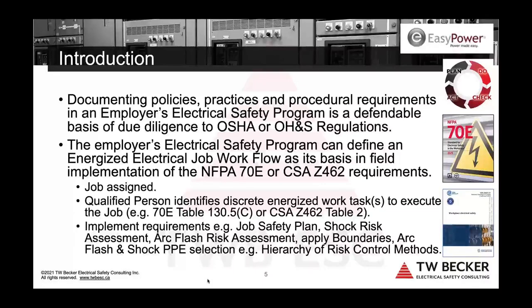So documented policies, practices, and procedure requirements need to be in an employer's electrical safety program. Well, not need, shall be; if you look to 70E and Z462, it's prescribed. Ultimately, this is what will give the employer defendable due diligence to OSHA regulations in the U.S. and OH&S regulations in Canada. I've seen several different electrical safety programs, actually more than several. And yes, you can frame your program differently, but I keep coming back to 70E and Z462 and saying these are work task-based standards. So it's about job workflow, energized electrical job workflow, discrete work tasks. And then, what do 70E and Z462 prescribe?